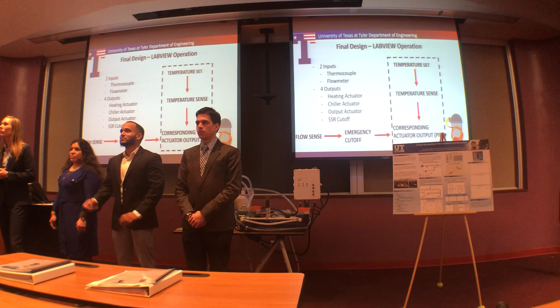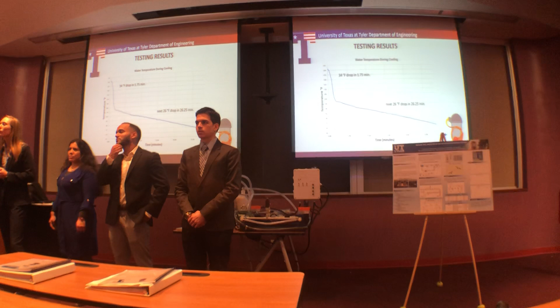And if I may, just one. Your charts aren't numbered, so I can't get back to the chart I wanted to reference. You have a temperature range versus flow rate curve, or data at least. I was curious, at those extremes of your temperature range, say your hottest temperature, if you can actually achieve that at your highest flow rate. So this test was actually done using our highest flow rate, in that we were able to achieve about 7 liters per minute for the highest temperature available.